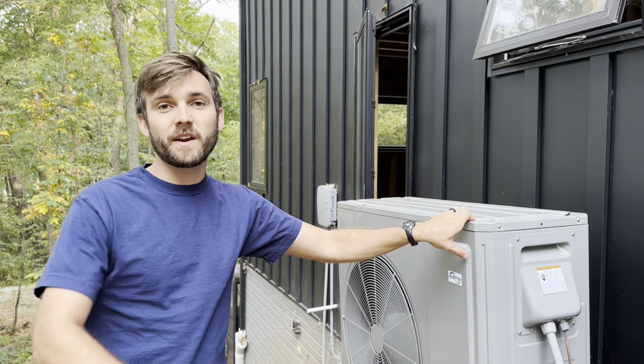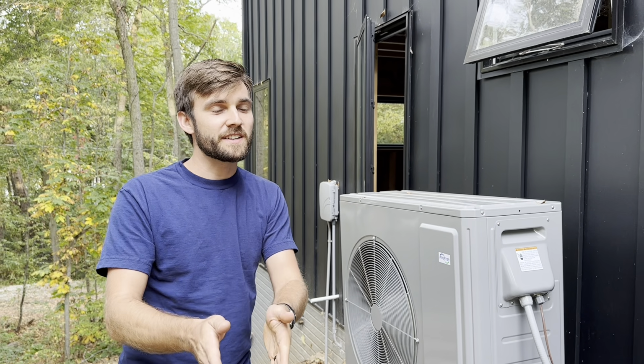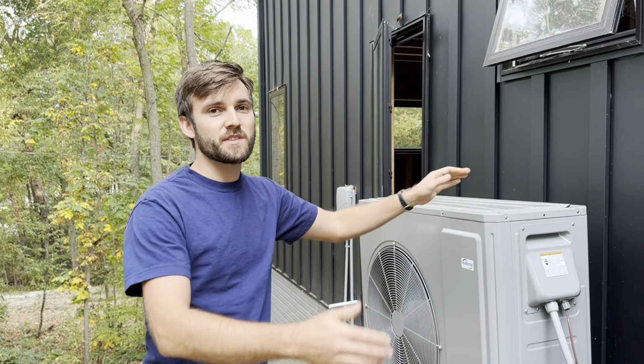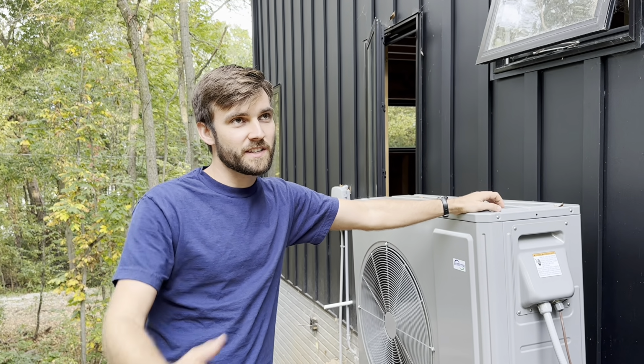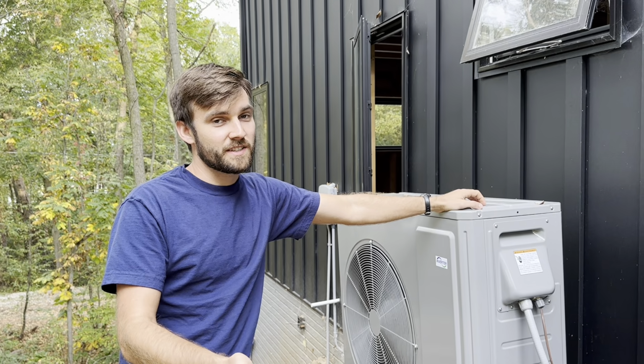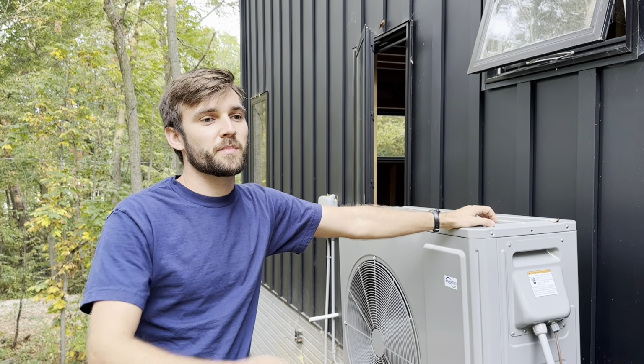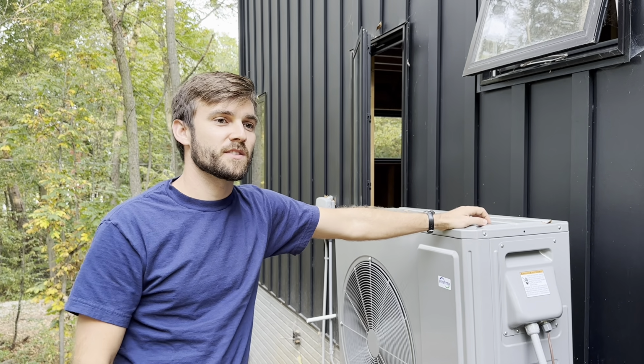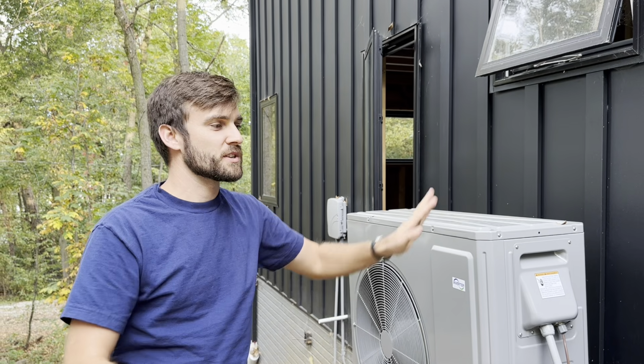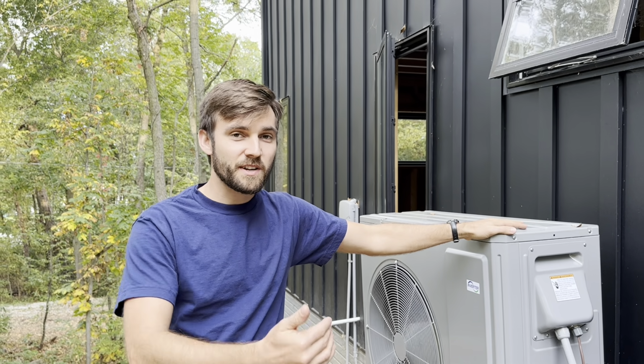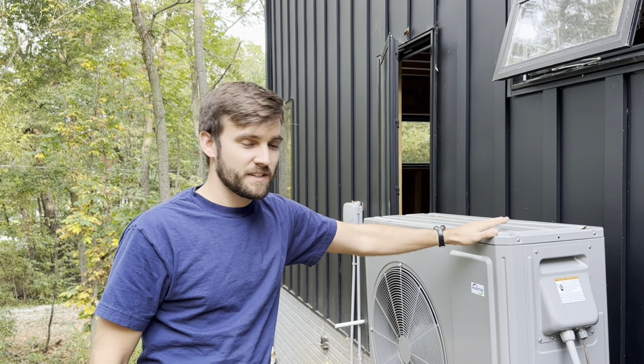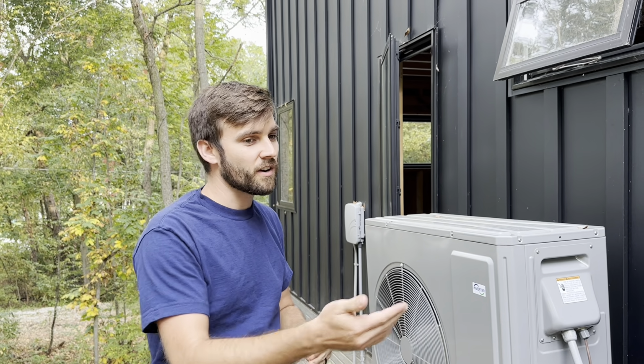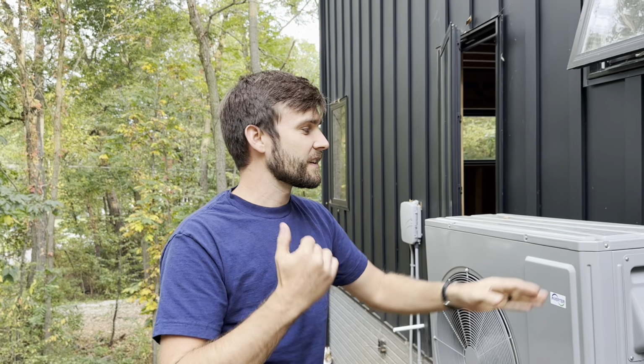Yeah, which apparently, watching the video from Gree, they said that the first batch of units that they had ordered in the United States didn't come with the communicating thermostat, but the next batches would. So they were telling people how to switch it over to 24 volt control, which I didn't want to do because 24 volt just gives the compressor an on or off signal, and it takes away all the fine tuning that these inverter driven compressors can do.